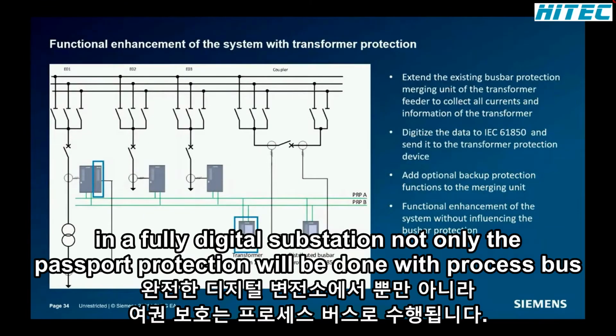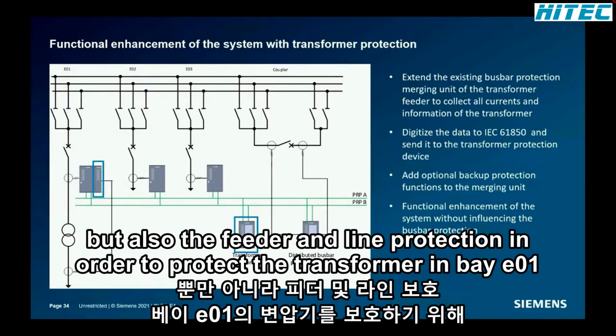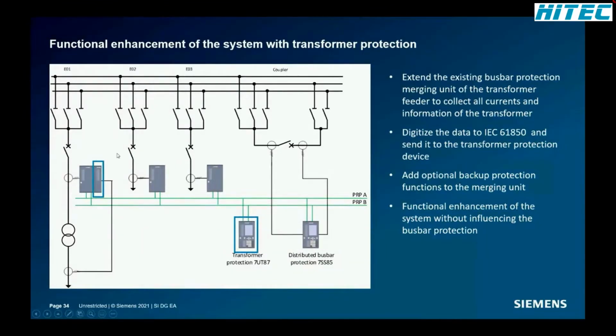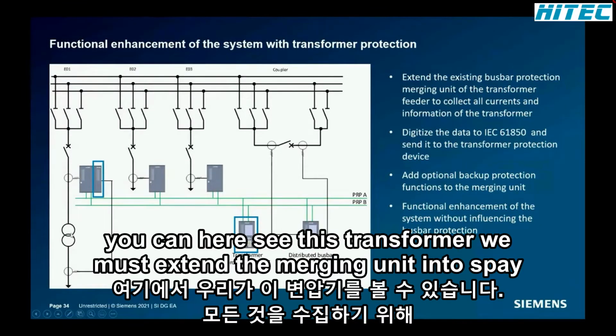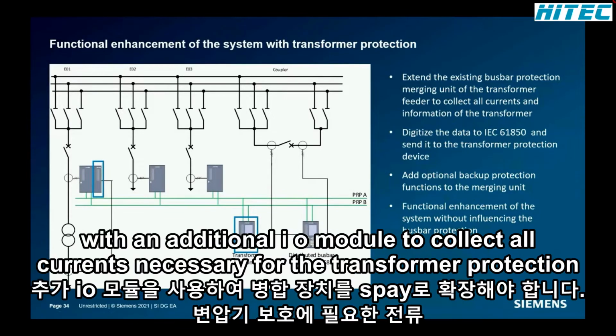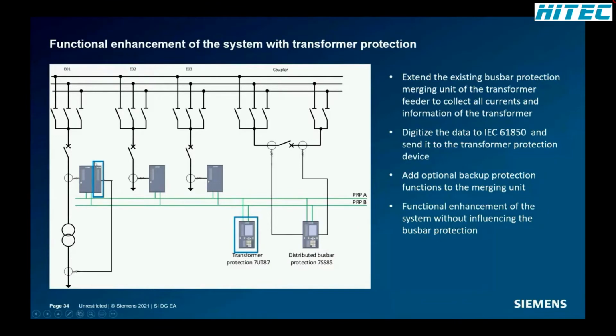In a fully digital substation, not only the busbar protection will be done with process bus, but also the feeder and line protection. In order to protect the transformer in bay E01, which you can see here, we must extend the merging unit in this bay with an additional I/O module to collect all currents necessary for the transformer protection.